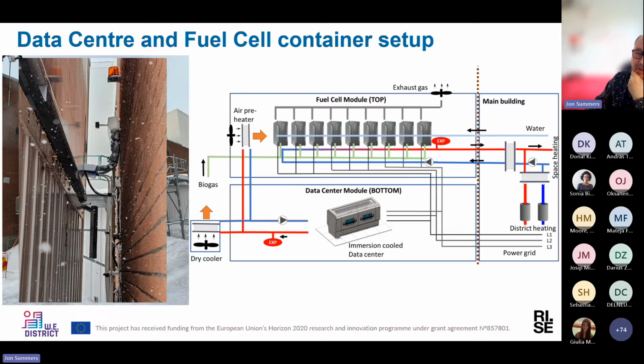The incoming air, the idea here was to actually preheat it. This concept was put together with our partners at IREC, the Research Institute for Energy in Catalonia. The idea is to use the heat from the data center, which when immersed is slightly hotter than you can get from air, but still low temperature, to take the outside air temperature and preheat it into the fuel cell container.